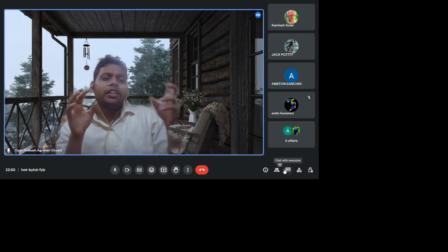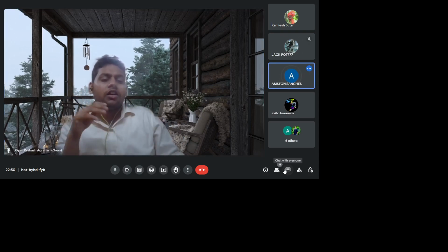Okay, and when this steam with high pressure gets condensed, do you have anything to say about this? Yeah, basically it's the reverse of steam hammering. In steam hammering, what happens is steam condenses into water and then sucks the water back. It's kind of similar to this, only when steam condenses, it leaves a void which can create a massive suction, which can suck the walls of your boiler inside.